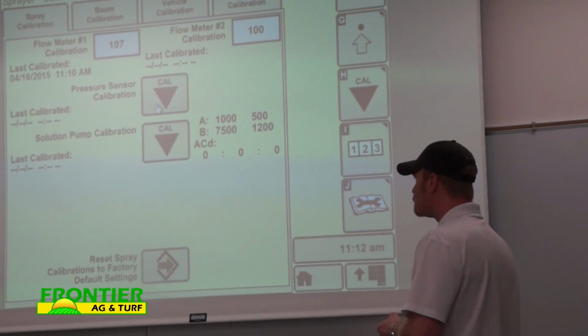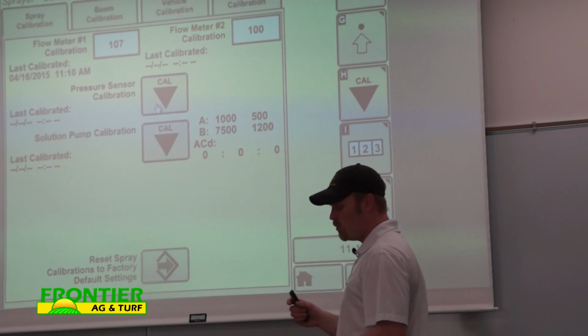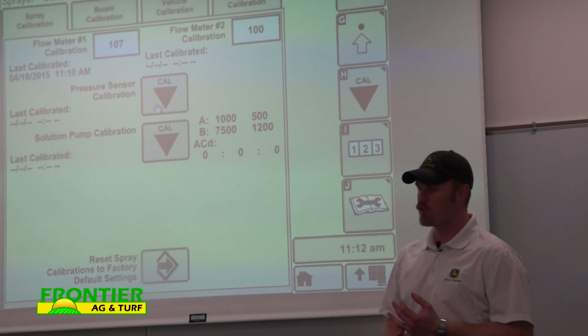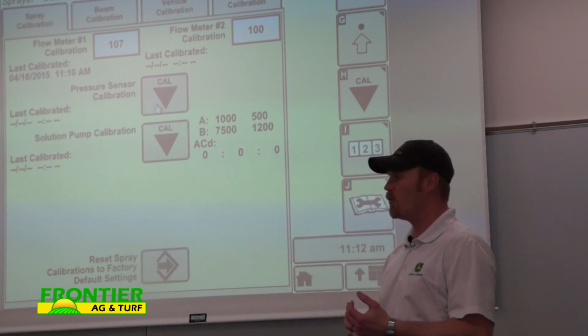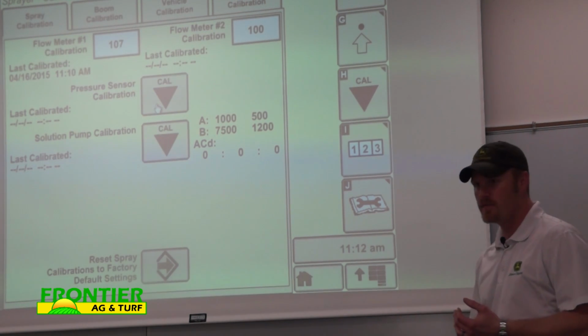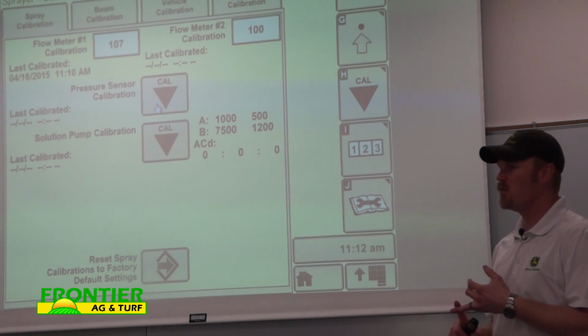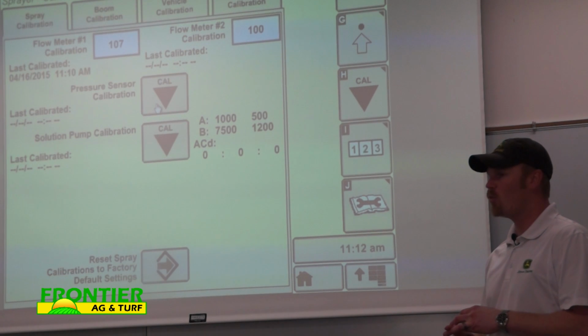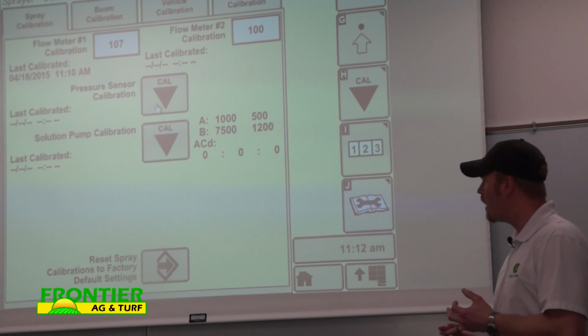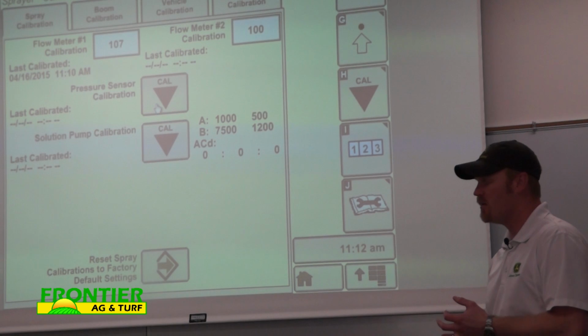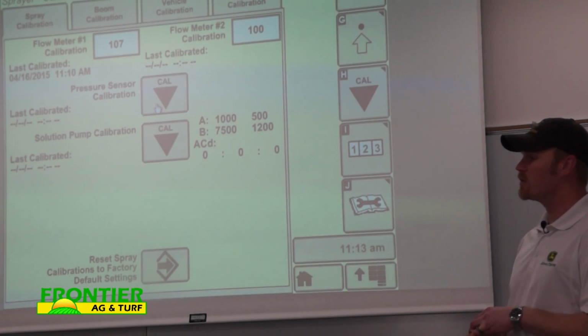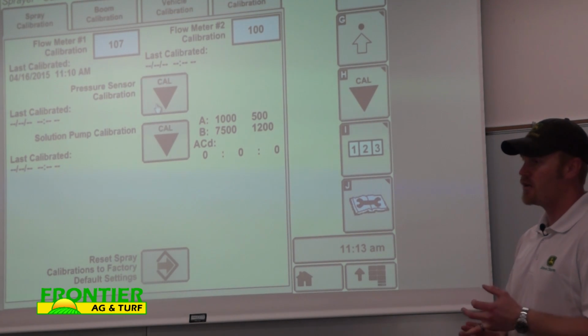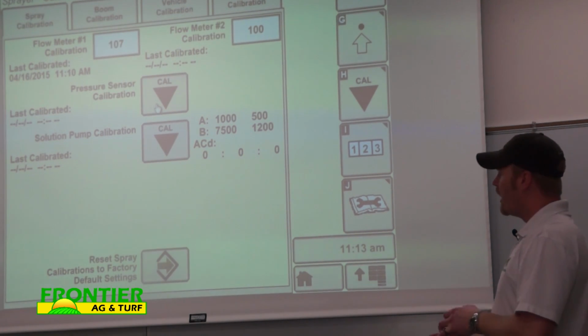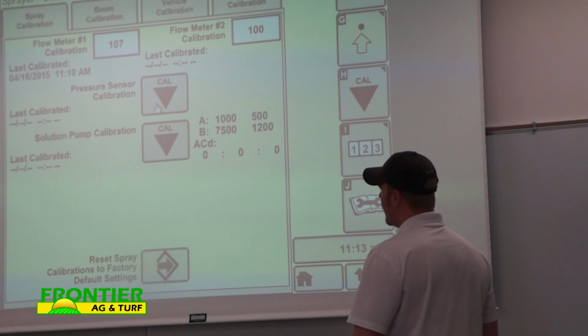Things change. For this calibration, one, I've got to have my hydraulic oil temperature up to at least 145 degrees Fahrenheit or above. Two, I want to calibrate with water in the system. Water is your most base mixing of chemical. Some guys do put chemical with 28%. You can calibrate at that, but water will still give you the most accurate reading. Okay? You've got to have those met before you can go through a cal.